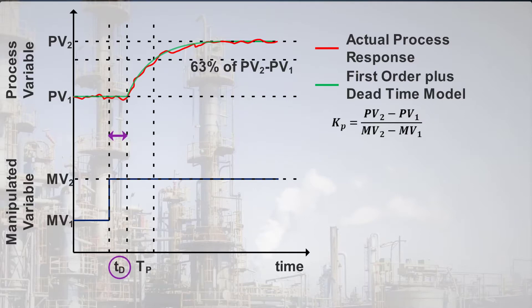The dead time, T sub D, is the time after the manipulated variable moves and before the process variable starts to move towards its steady-state value. Dead time can happen because we don't measure a change until after it's had time to move down a pipe or through a vessel.